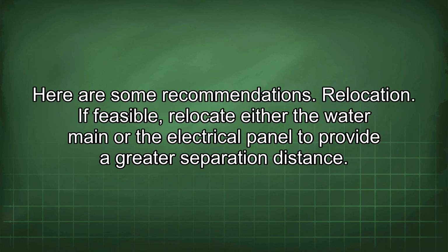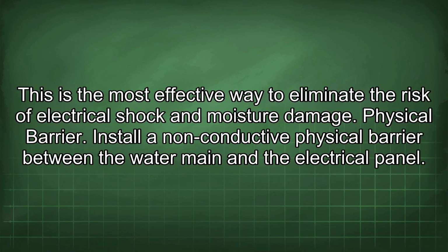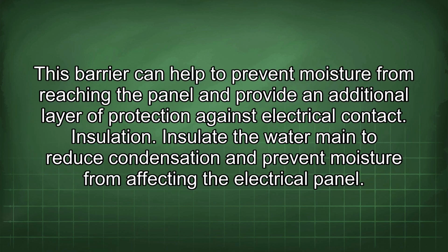Here are some recommendations. Relocation. If feasible, relocate either the water main or the electrical panel to provide a greater separation distance. This is the most effective way to eliminate the risk of electrical shock and moisture damage. Physical barrier. Install a non-conductive physical barrier between the water main and the electrical panel. This barrier can help to prevent moisture from reaching the panel and provide an additional layer of protection against electrical contact.